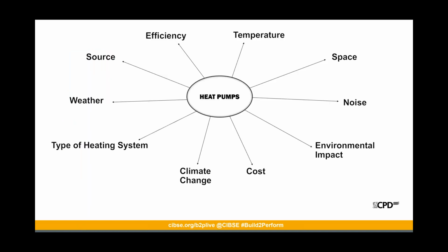When designing heat pump systems, there are a few things that we have to take into consideration, such as the source. Is it going to be an air source heat pump, a ground source heat pump, etc.? Temperatures are also crucial: what we're looking to achieve and what temperatures are available under external conditions. For example, in warmer climates, the COP would be increased since the weather is quite important.